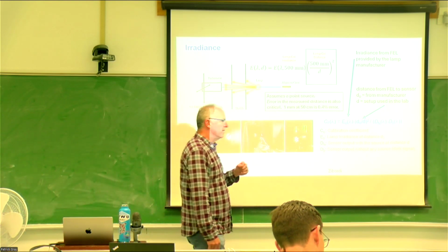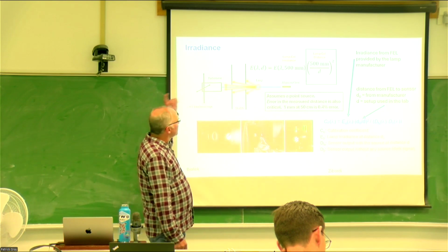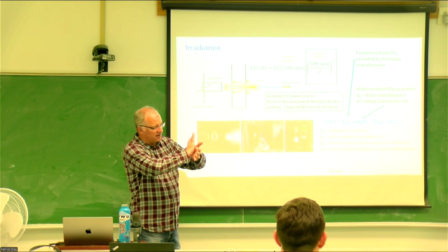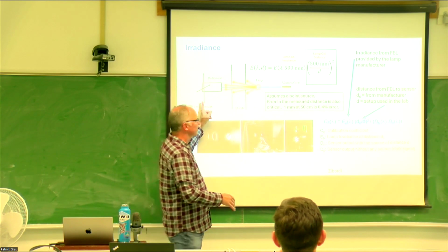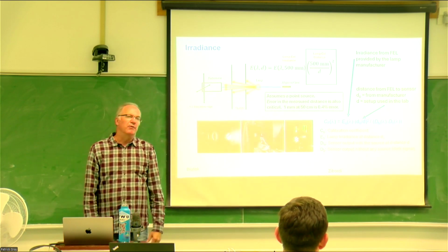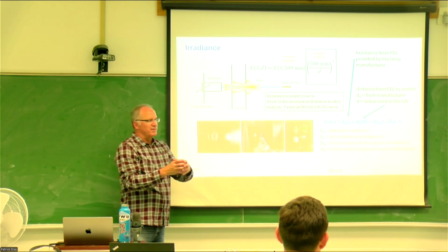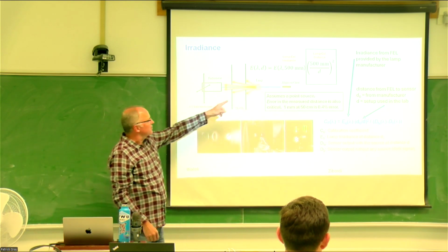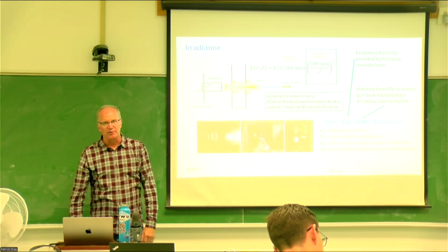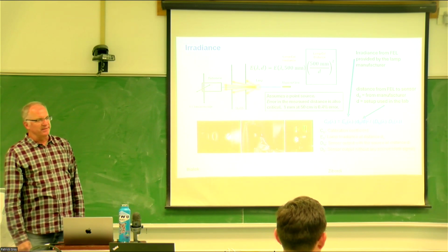For irradiance, yes, it goes right up against the cosine collector: the distance from the cosine collector to the center of the filament. When you put the FEL on a fixture to light it up, there are known distances, and you have to get out calipers so we can recalibrate them. So it's a meticulous process.